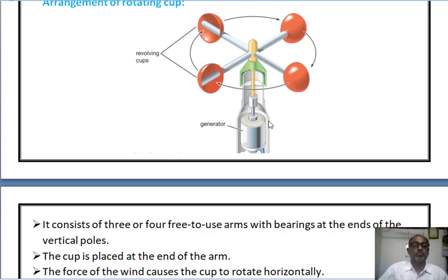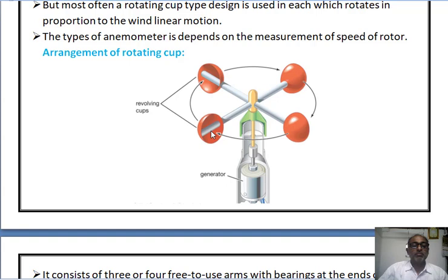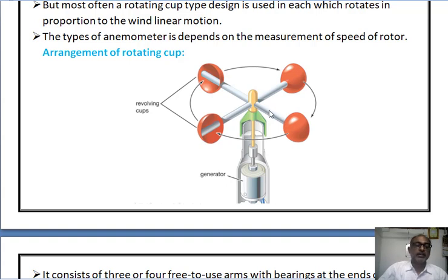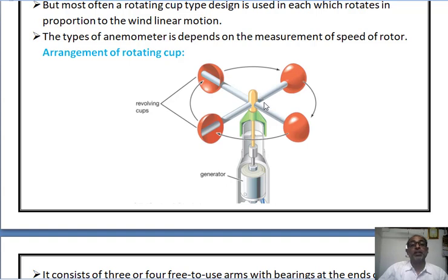In the electric anemometer, the armature of a permanent magnet type DC generator is connected at the shaft of the rotating cups. Whatever EMF is induced in the armature winding of the DC generator depends on the shaft speed and the wind velocity. This voltage is applied to the voltmeter, whose dial is calibrated in meters per second. The signals from the armature are also applied to a signal recorder or data logger.